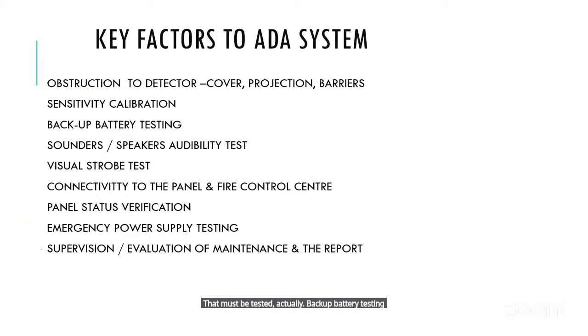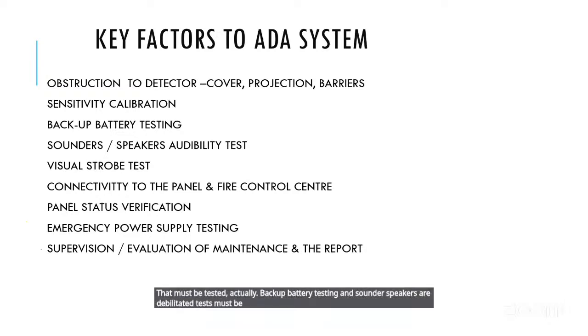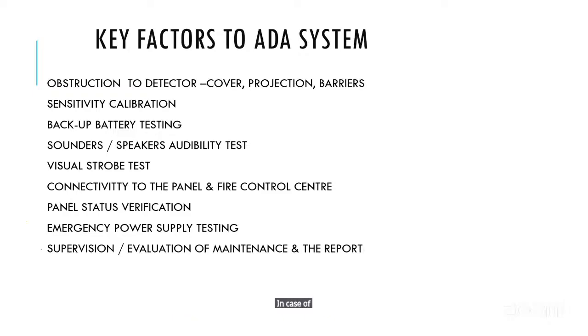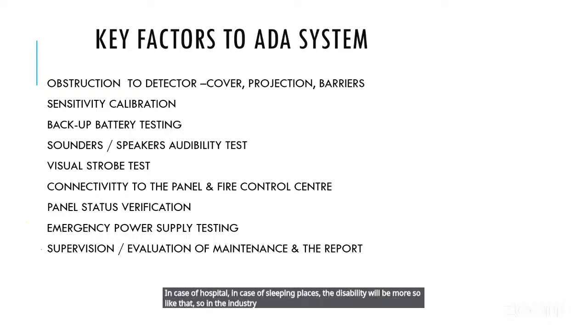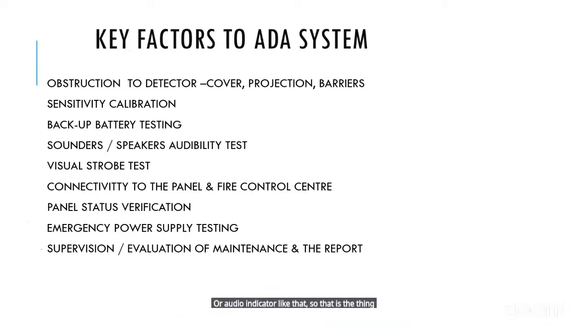And the audibility test of the sounders and speakers must be conducted. A decibel meter is available; you have to use it. You have to understand whether it is 90 decibels or 80 decibels, and the decibel level will differ from place to place. In hospitals and sleeping places, the decibel level will be higher. In industry where there is more sound, your decibel level should be higher. Where the sound is so high that the decibel level cannot be increased, you have to give a visual indicator or audio indicator like that. That is the thing we already spoke about. And the visual strobe test, that I have covered.